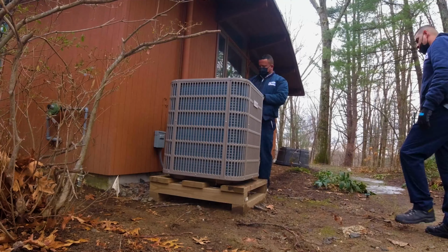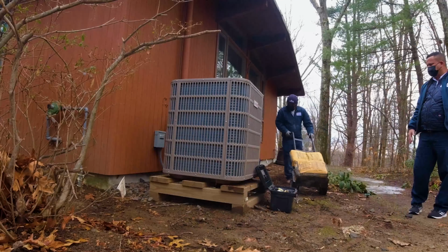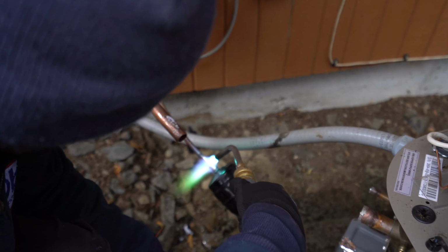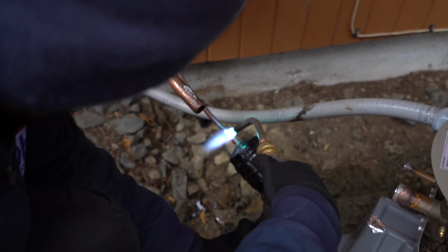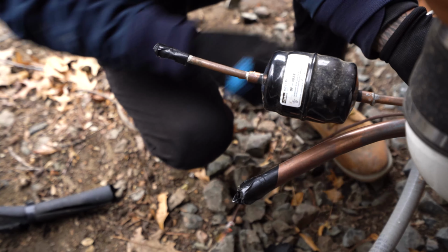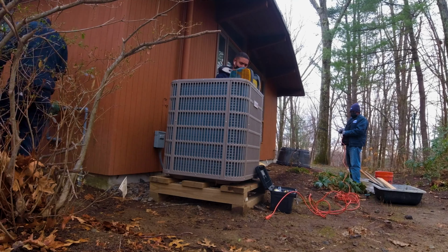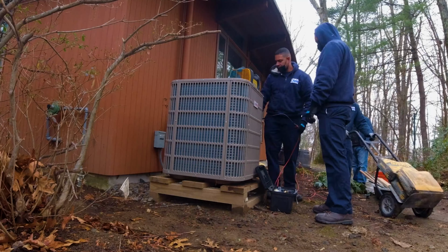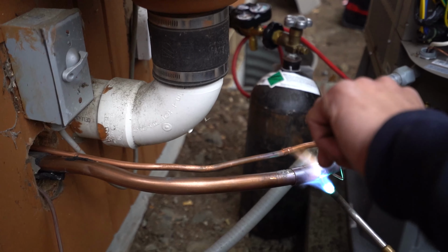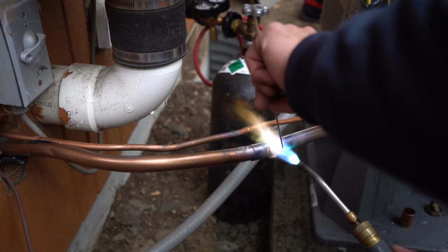So going outside of the house, as you see, we found a few problems. The first one, just like they did inside, unfortunately they used the plumbing solder to connect the copper lines. This is not acceptable. This system right now has 0 refrigerant in. Everything had leaked because they used the improper solder.